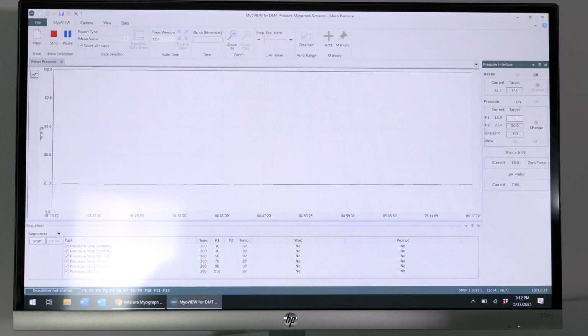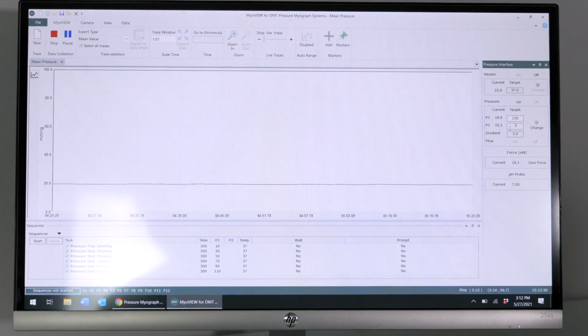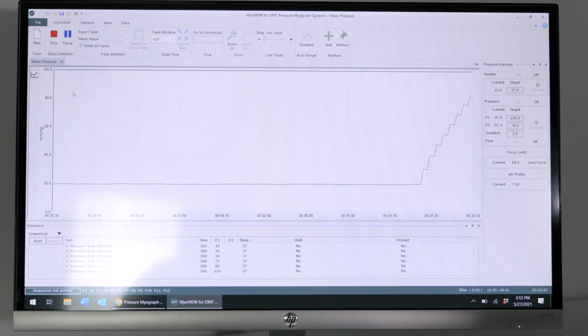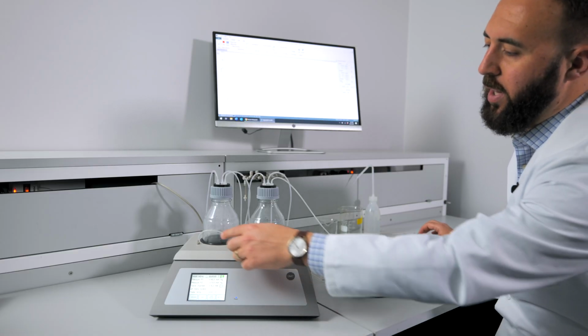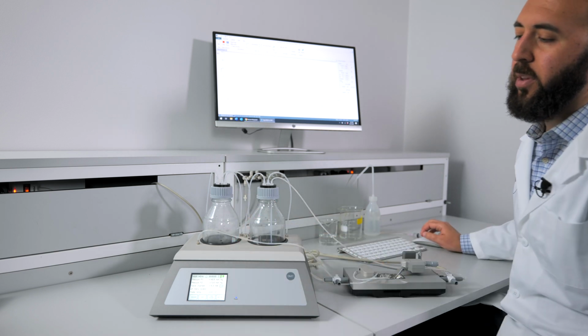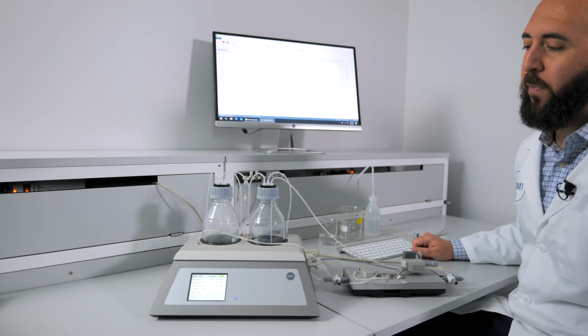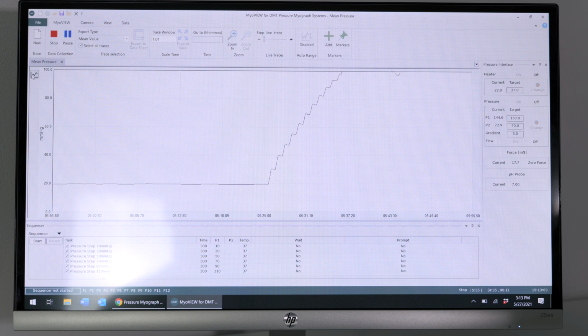You should then change your pressures for P1 to 150 and P2 to 70. Turn on pressure and make sure that flow is on, which will then push all of the buffer into the P2 waste bottle. You can check your lines to make sure that there is only air in the lines and no more buffer.